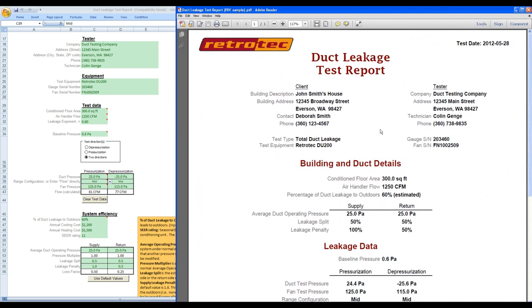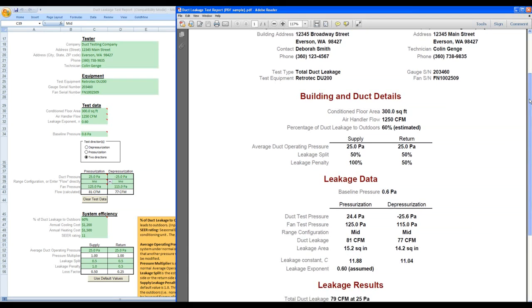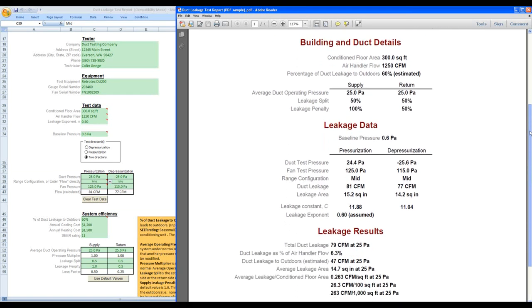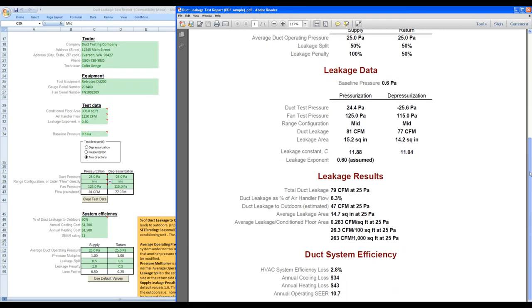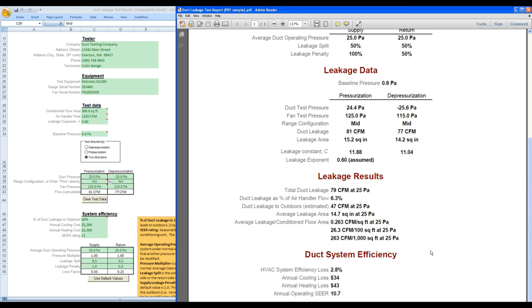Here is a sample of the duct leakage test report. Get results as leakage rate, leakage area, duct leakage as a percentage of air handler flow, leakage per conditioned floor area, duct system efficiency loss, and annual cooling and heating losses.